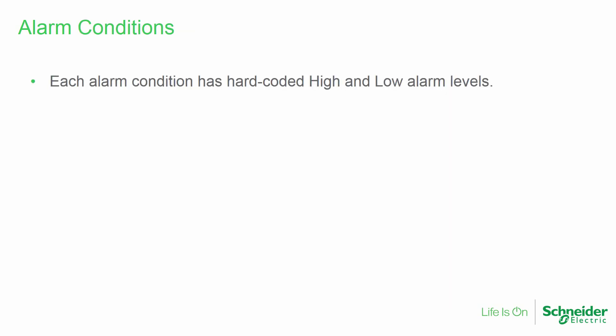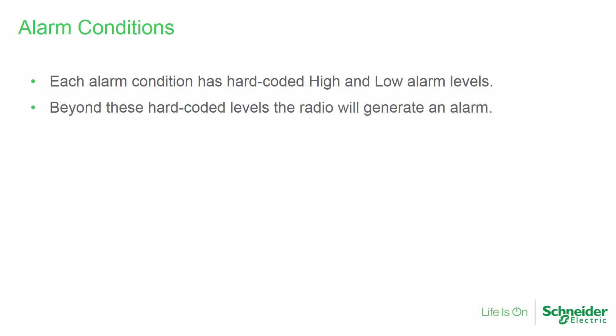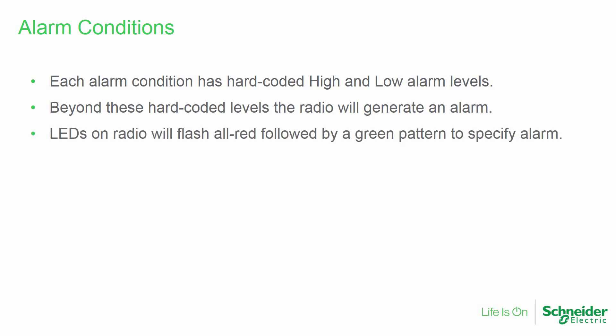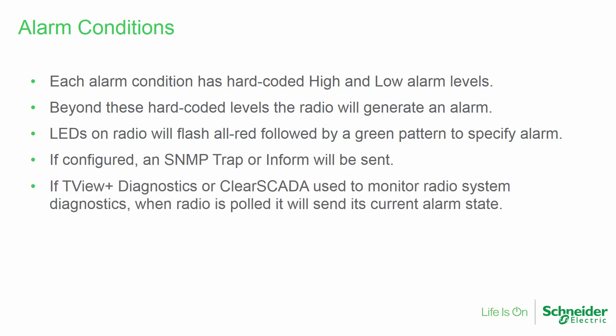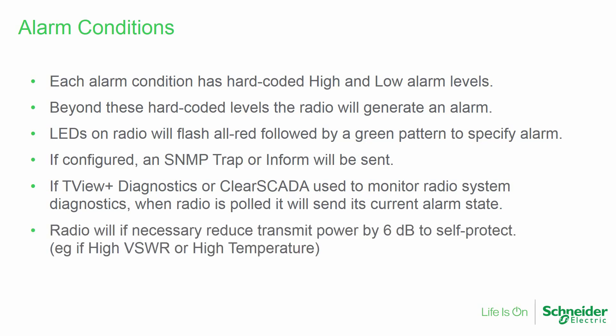Each alarm condition has hard-coded high and low alarm levels. Beyond these levels, the radio will generate an alarm. At this point, the LEDs on the radio will flash all red, followed by a green pattern which specifies the alarm. If SNMP is used, a trap or inform will be sent. If TView+ Diagnostics or clear SCADA is used, when the radio is polled, it will send its current alarm state. Note that a TRIO-Q radio will, if necessary, self-protect by reducing its transmit power by 6 dB, for example if a high VSWR or high temperature condition is detected.